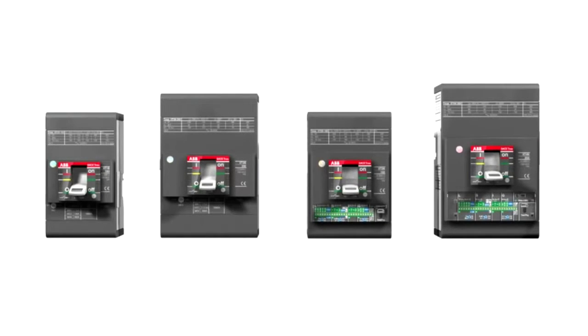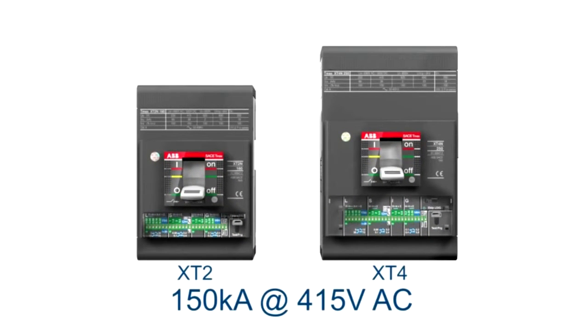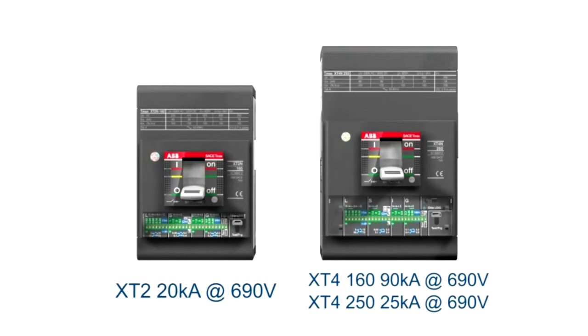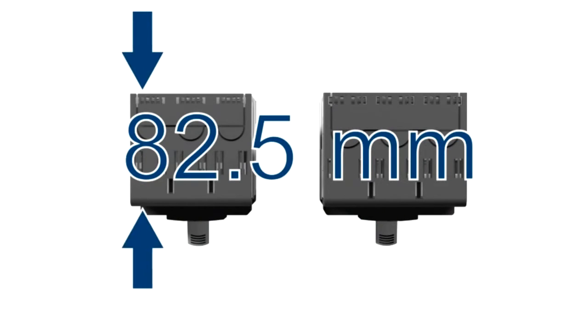T-MAX XT2 and XT4 represent the most advanced models in the range, with high breaking capacities of up to 150 kA at 415 volt, as well as high breaking capacities at 690 volt. They have a coordinated depth of 82.5 mm and can be mounted on a base plate with a smaller window.